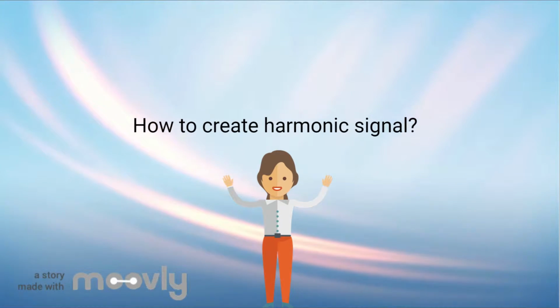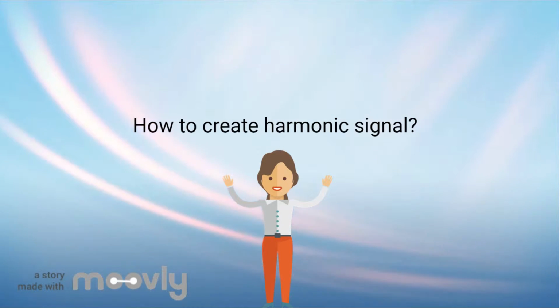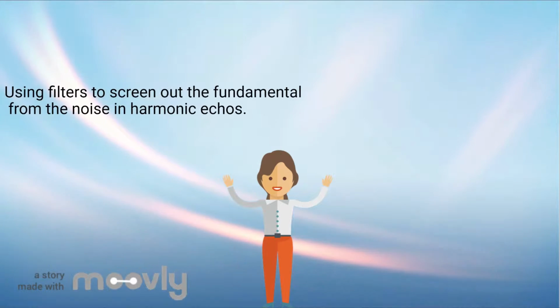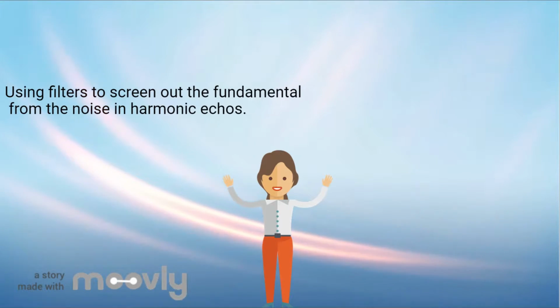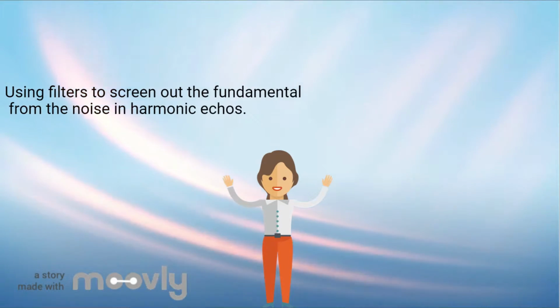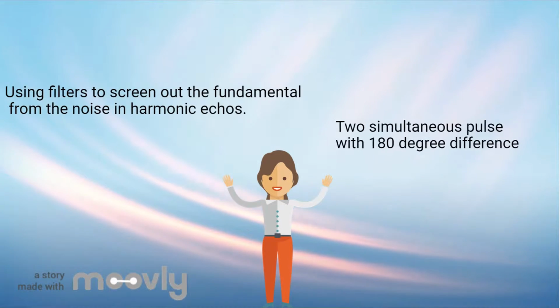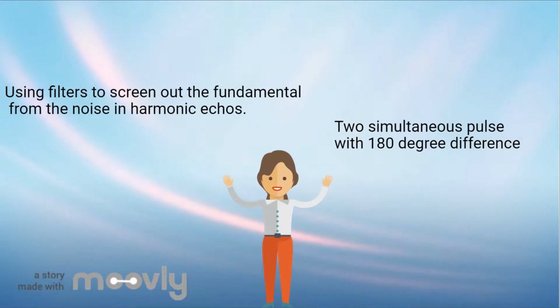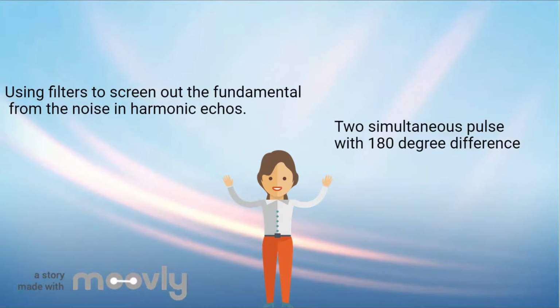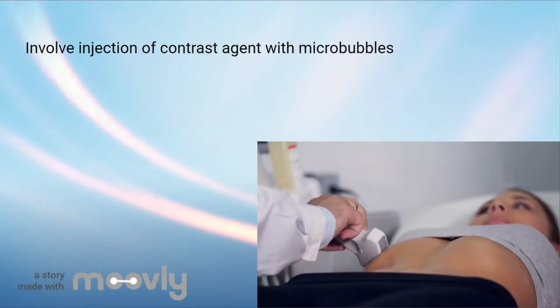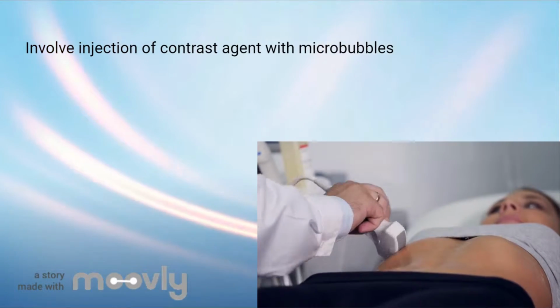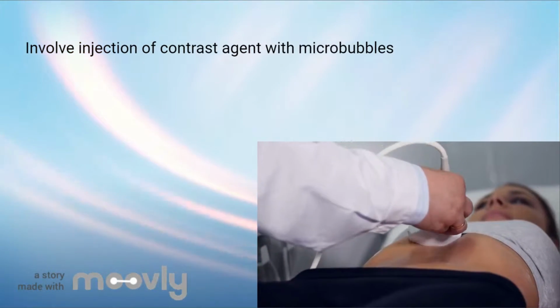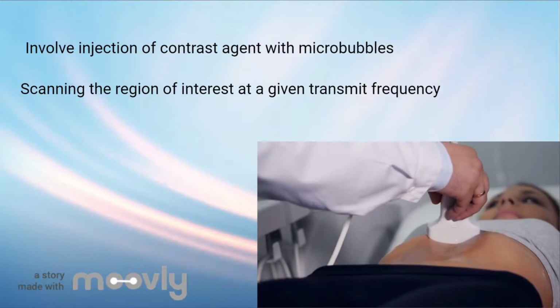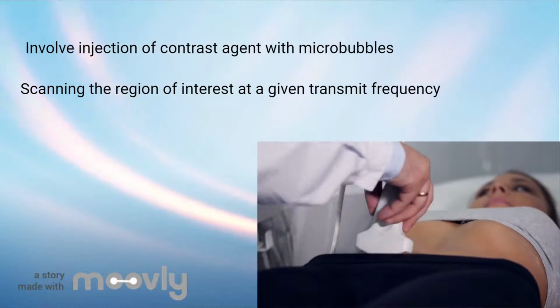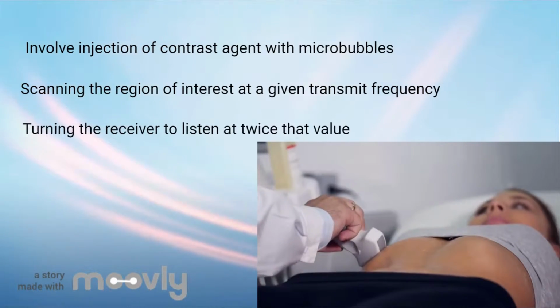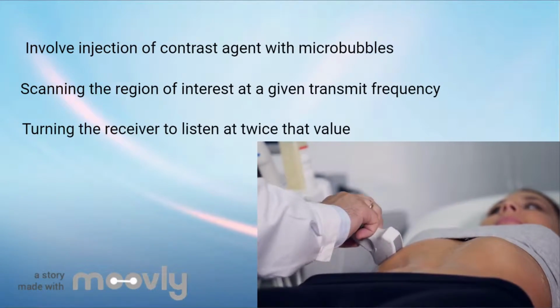There are two different processes that can be utilized to create harmonic signal. First, by using filters to screen out the fundamental from the noise in harmonic echoes. Second, by using two simultaneous pulses with a 180 degree difference. Harmonic imaging can involve injection of contrast agents with the appropriate microbubbles, then scanning the region of interest at a given transmitted frequency and tuning the receiver to receive double the amount.